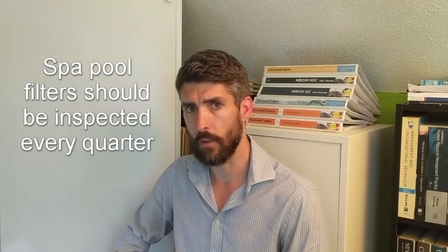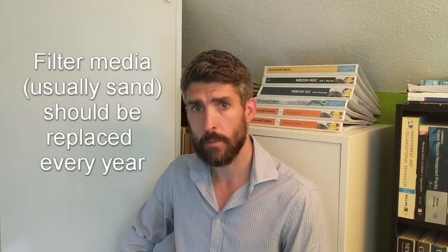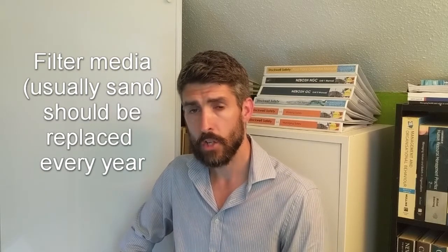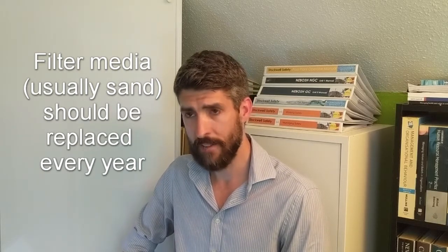That's usually a job that's contracted out to a third party contractor as part of a service level agreement. Media, that's to say the sand in most commercial swimming pool filters, should be replaced much more frequently than a typical swimming pool would get its media replaced. It should be done annually for a spa pool. So every year the filter should be emptied of sand and replaced with new.